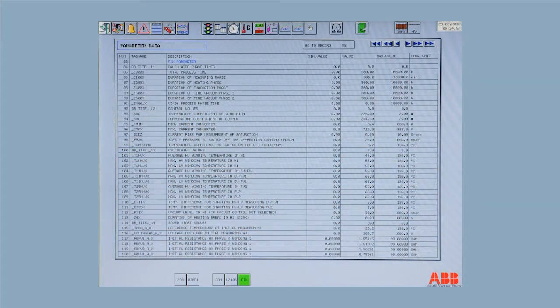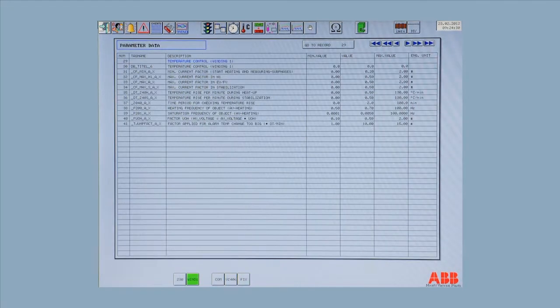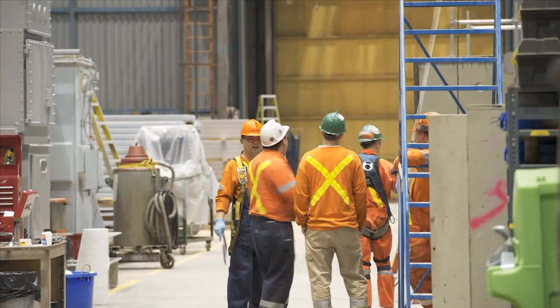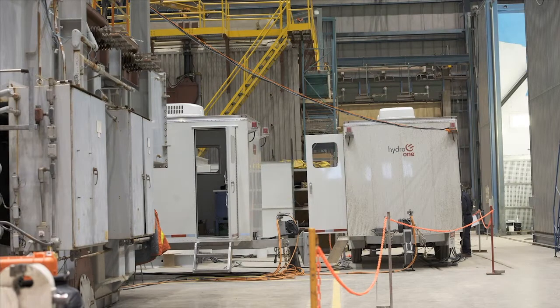Altering of the general parameters and the fixed values should only be done in consultation with Micafil. Process parameter sets should only be elaborated by an experienced transformer drying specialist. All maintenance work should be done by qualified personnel. Pre-start physical connections. The completely assembled transformer, including bushings and tap changers, is placed in front of the vacuum and heating equipment. The following work has to be done before process start.